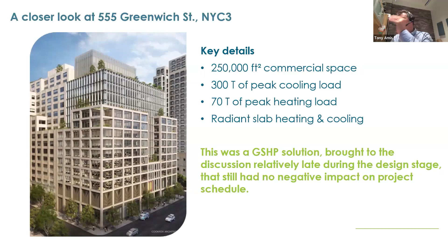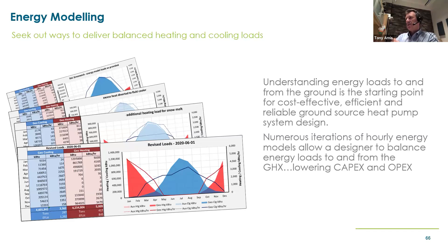But one of the things that is so important with geothermal systems is understanding the heating and cooling load of a building every single hour of the year, because we want to design these systems to outlast the building. Ultimately, what we're looking to do is to treat the ground like a battery. What we take out in the winter to deliver heating to the building, we cool the ground. We want to put that heat back in the summertime and deliver a lot of cooling, and effectively recharge the battery. I'm going to come back to that towards the end of the slides here.